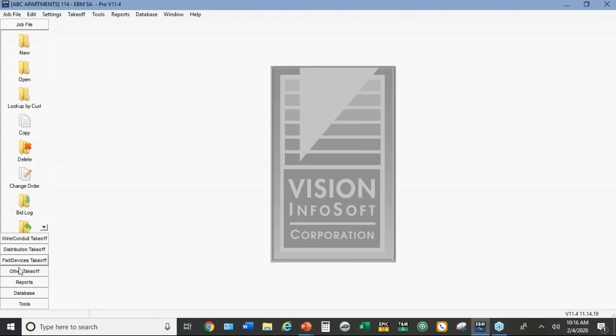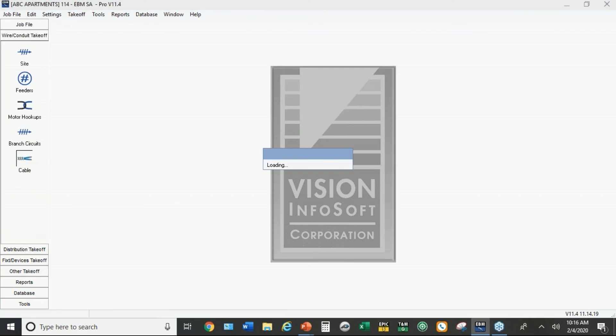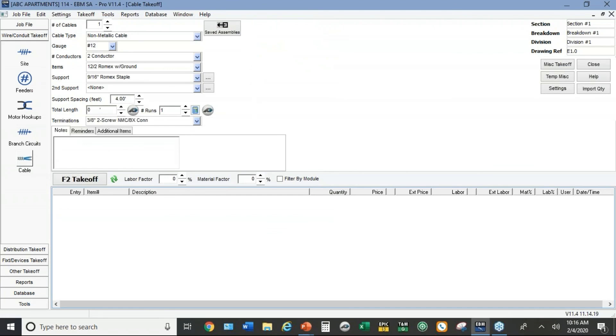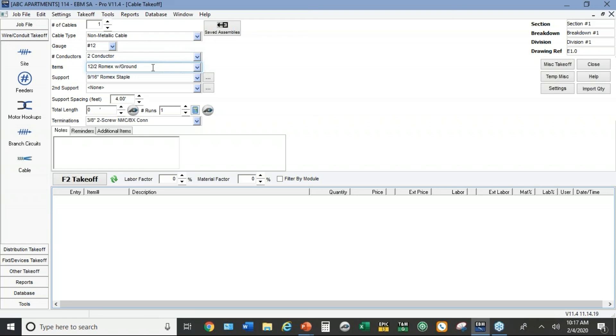So what I did here in the takeoff, under the cable takeoff, I defaulted it to Romex instead of MC cable like it is in the commercial version. So you've got your regular non-metallic Romex here. You also can do UF cable, and there's also service entrance cable in here. But I set the default to Romex because that's usually the way the apartment parts of the job are wired on multifamily residential.